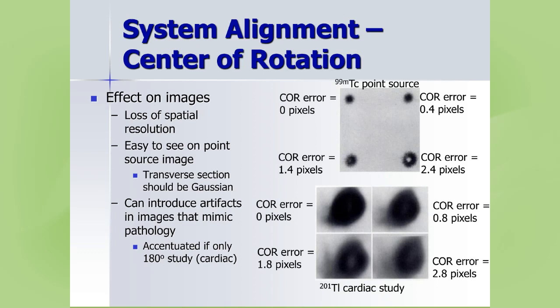On a cardiac study, a COR error of 2.8 pixels starts to look like a defect on the heart, introducing apparent pathology because the heads are misaligned. This is especially accentuated when using 180-degree head alignment in cardiac studies. For accreditation, testing is required per manufacturer timetable and methods. If in doubt, do it at least monthly. Collimators not frequently used must still be tested prior to patient exams.